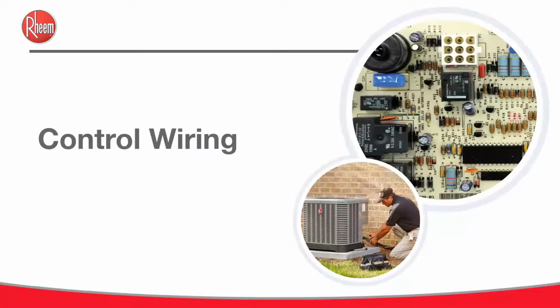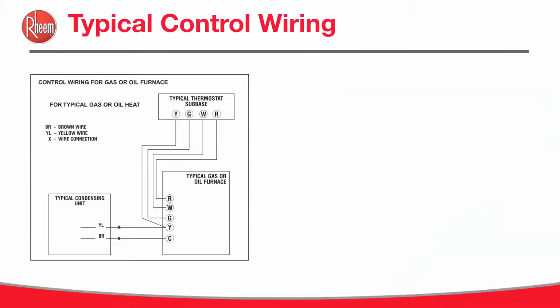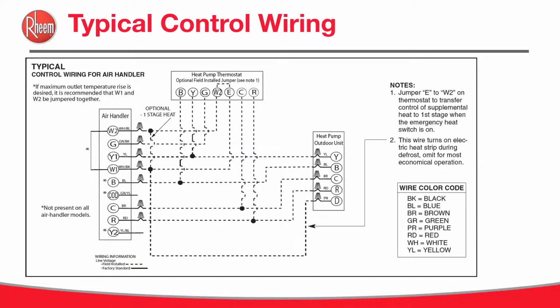So let's look at the similarities and differences between wiring on an AC and a heat pump. On an AC, the wiring can be as simple as connecting to the Y and C on the outdoor unit, off the board to the outdoor unit. With heat pumps, you have extra connections, which include the ability to switch from heating to cooling, as well as defrost and auxiliary heat for defrost mode. So as you see here, you've got a D, which brings on your auxiliary backup heat when you're in defrost mode. Why, you ask? Well, if you don't have backup heat or auxiliary heat, we'll call it, then you're basically in air conditioning mode, so it gets cool in the house. So you want to put that on.